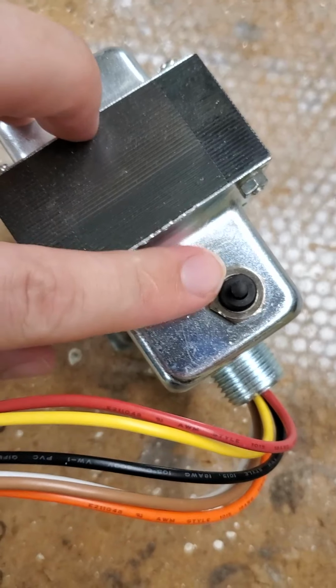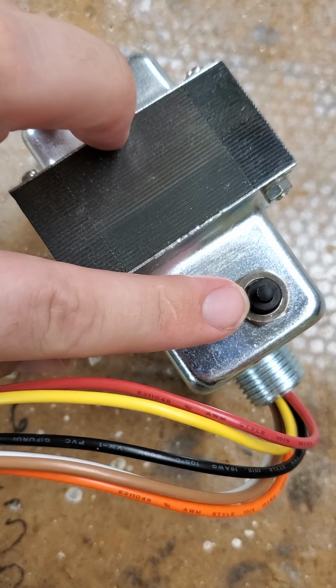So this thing that I'm poking at is a circuit breaker. Not every transformer will have one of these, but it's actually a useful tool for troubleshooting. So if you ever come into a building and say the power's off, and then you go look at the transformer, you're not getting power out of the transformer. One of the first things I would do would be press this button and make sure it's not tripped. If it's tripped, you'll actually hear a physical click as it goes inside, and if it's not tripped, you won't have that.